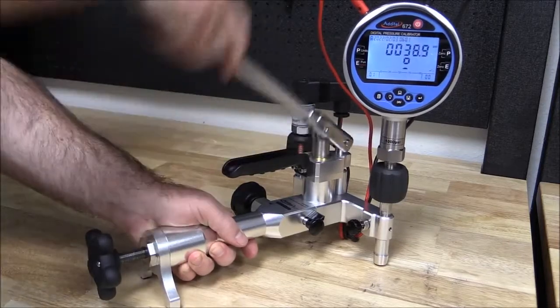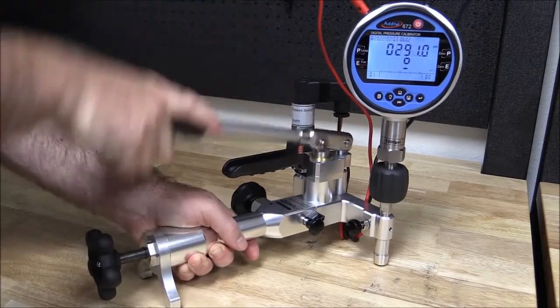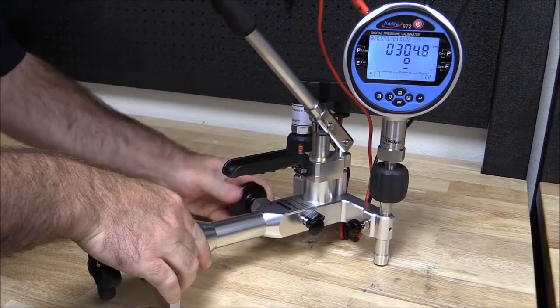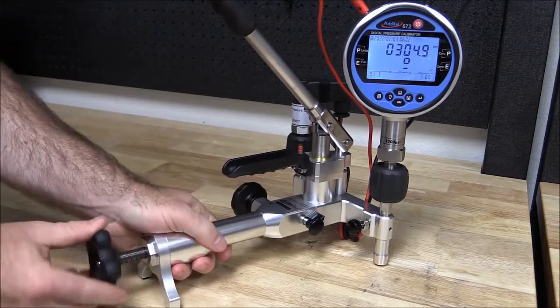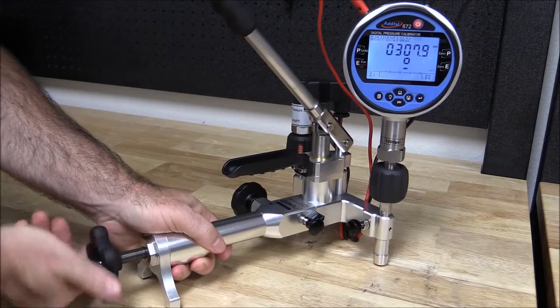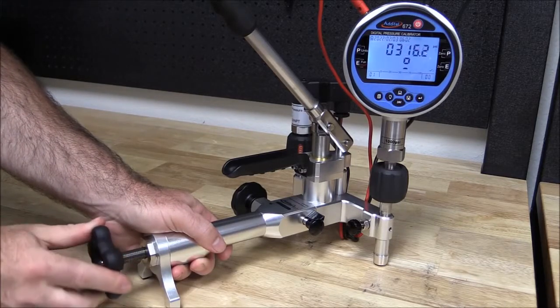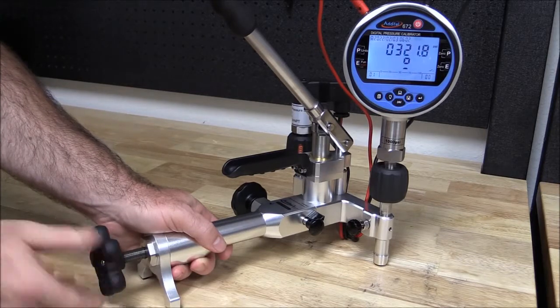With Additel pneumatic pumps, pressure can simply be generated with the hand pump. As we approach the set point pressures, we can close the isolation valve and use the screw press for fine adjustment. With Additel's unique pump design, the isolation valve isolates the calibration volume from the hand pump and the check valve, providing more stable measurements than traditional hand pumps.